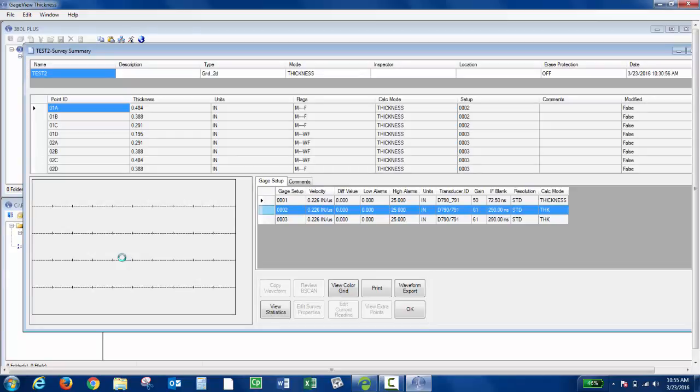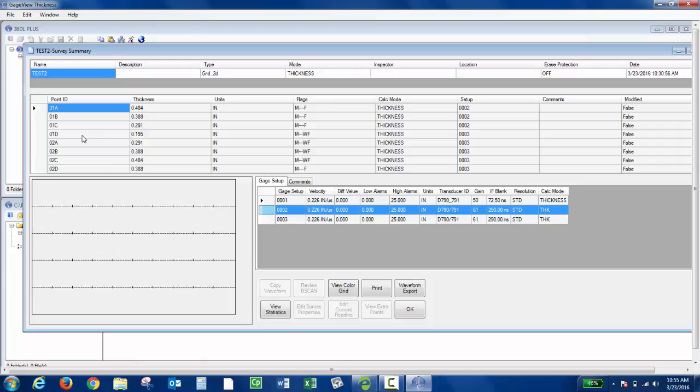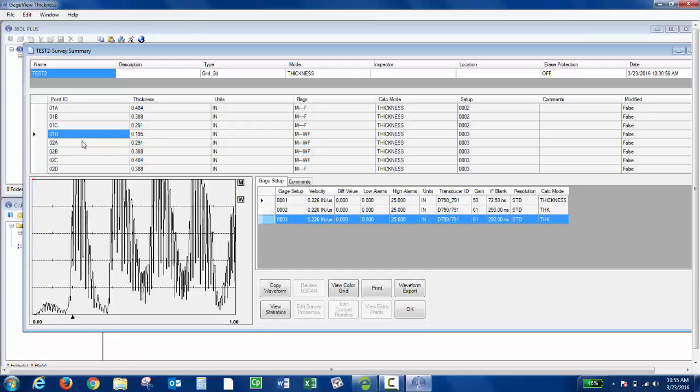The thickness measurement table is displayed in the top list box. The gauge setup table displays the calibration details. If a waveform was saved, it would be displayed on this screen when I select that ID. Some I saved A-scans to. If I click it, you'll see the actual A-scan.